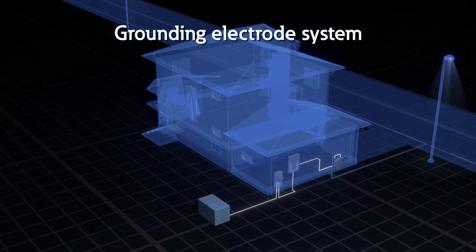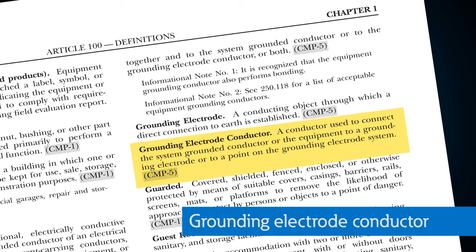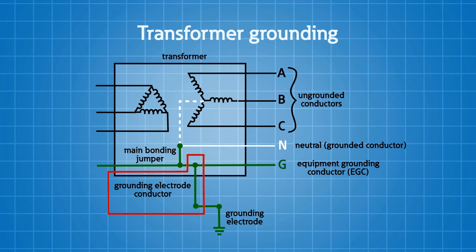The grounding electrode system is when we pull all of those grounding electrodes together. Every grounding electrode on that site — whether it be the UFER ground, the water pipe, or other means identified in the NEC — we have to pull all of those together as a system. Now let's talk about the grounding electrode conductor: this is the conductor used to connect the system neutral conductor, grounded phase conductor, or the equipment to the grounding electrode system.